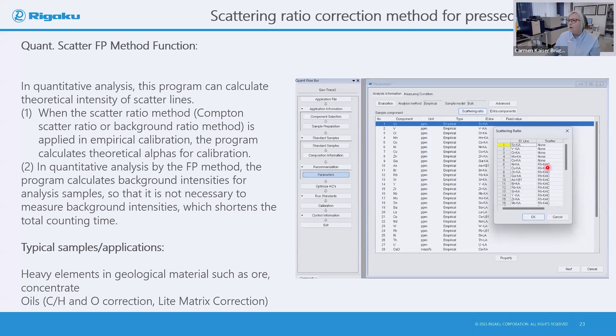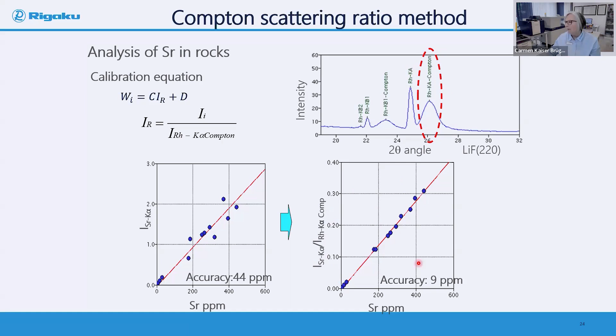So here we can see an example of a trace element where we just plotted an empirical calibration, where we plotted the concentration in ppm versus the intensity of the analyte line, and you can see there's a lot of scatter. But the moment that we can measure the Compton line for each and every standard, and we can ratio the analyte line with the Compton line, we suddenly get a very improved regression and accuracy on this calibration line. So this is a very useful method that we can utilize.